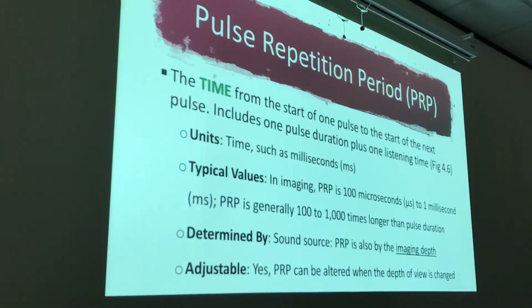On time is also known as what, guys? Talking time, but more specifically to our parameters, also known as our pulse duration, right? Our on time is also known as our pulse duration. We already determined that we can't change that. That's already fixed, right? The transducer fixed the pulse duration. So when we adjust our depth, the only thing we're changing is the listening time. So that's why I have shallow and deep right here, because as we go deeper, the machine is gonna need a longer listening time to wait on those reflected sound waves.